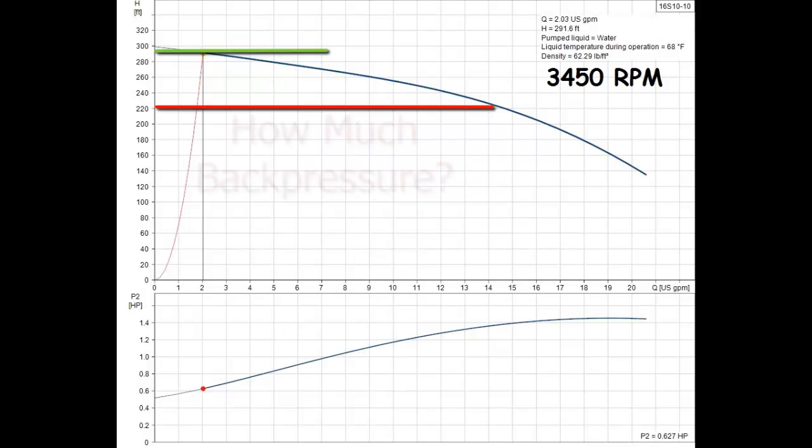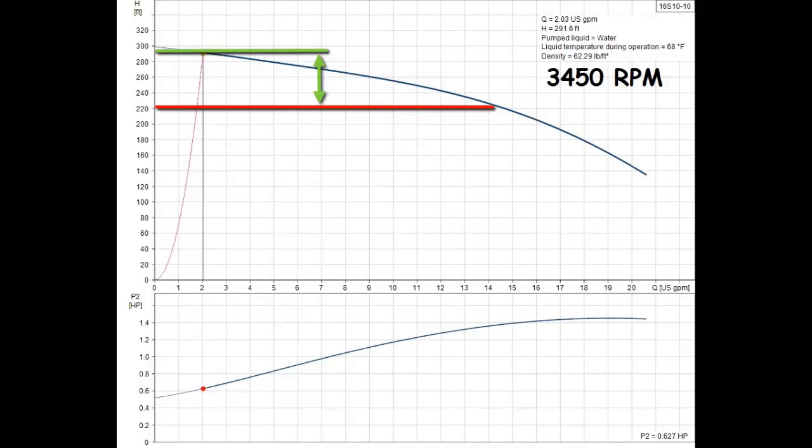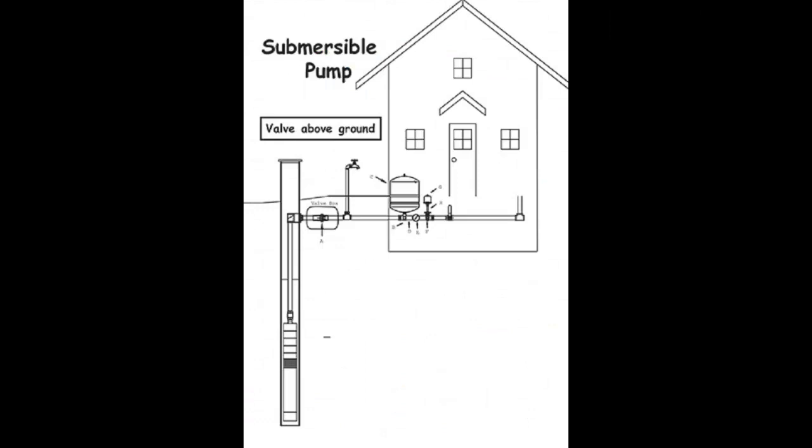However, the amount of back pressure needs to be figured to make sure the pressure rating of the pipe and the valve is adequate. The pump curve is also used to figure back pressure. When figuring back pressure, we always use the worst case scenario, which is the high static water level, not the pumping level.